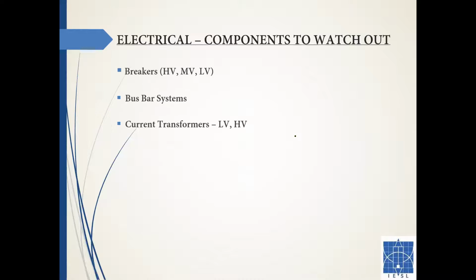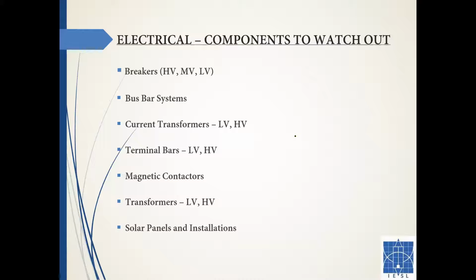So we have seen enough electrical components. I think it's clear that all the components need to be checked: breakers, current transformers, terminal bus, contactors. Bus bar systems can be really complex because you have a lot of connecting bolts. And remember what I told about emissivity? These bare copper bars you have in the bus trunking systems and bare bus bar distribution systems have really low emissivity. Using thermal imaging, you cannot capture the true photons coming from the bus bar systems, which makes the job of the thermographer really difficult.